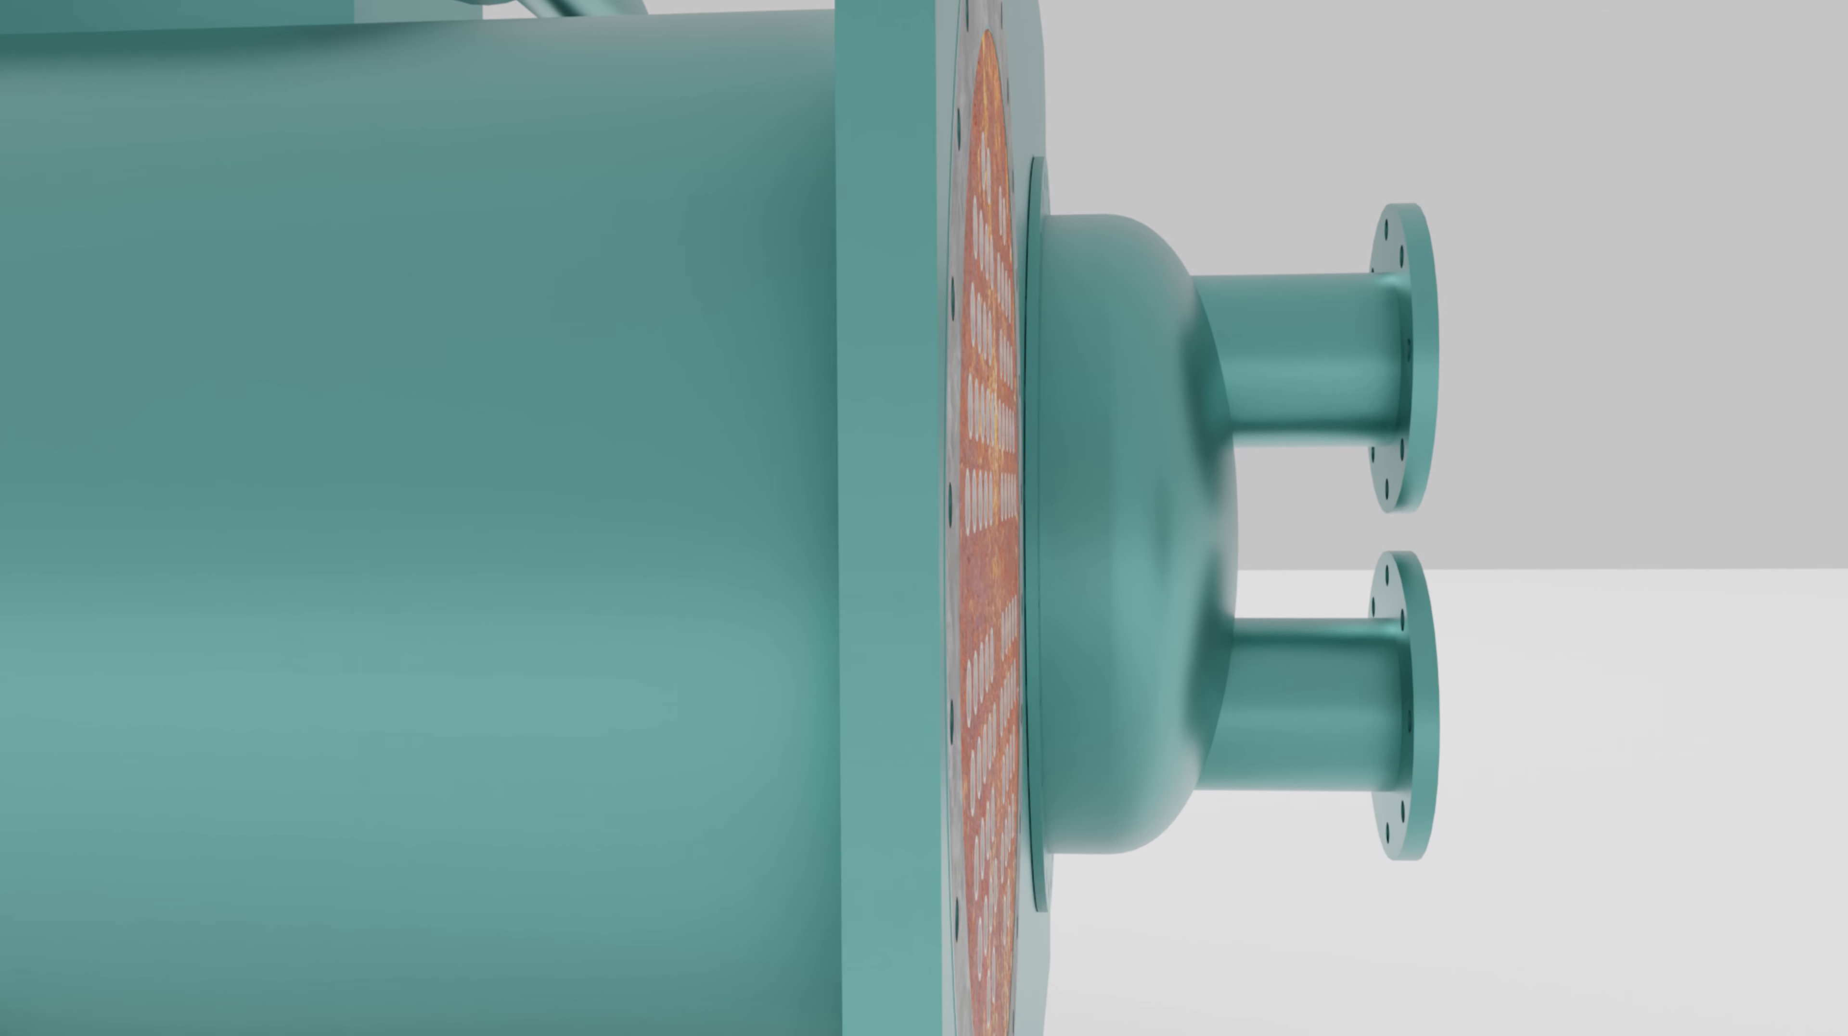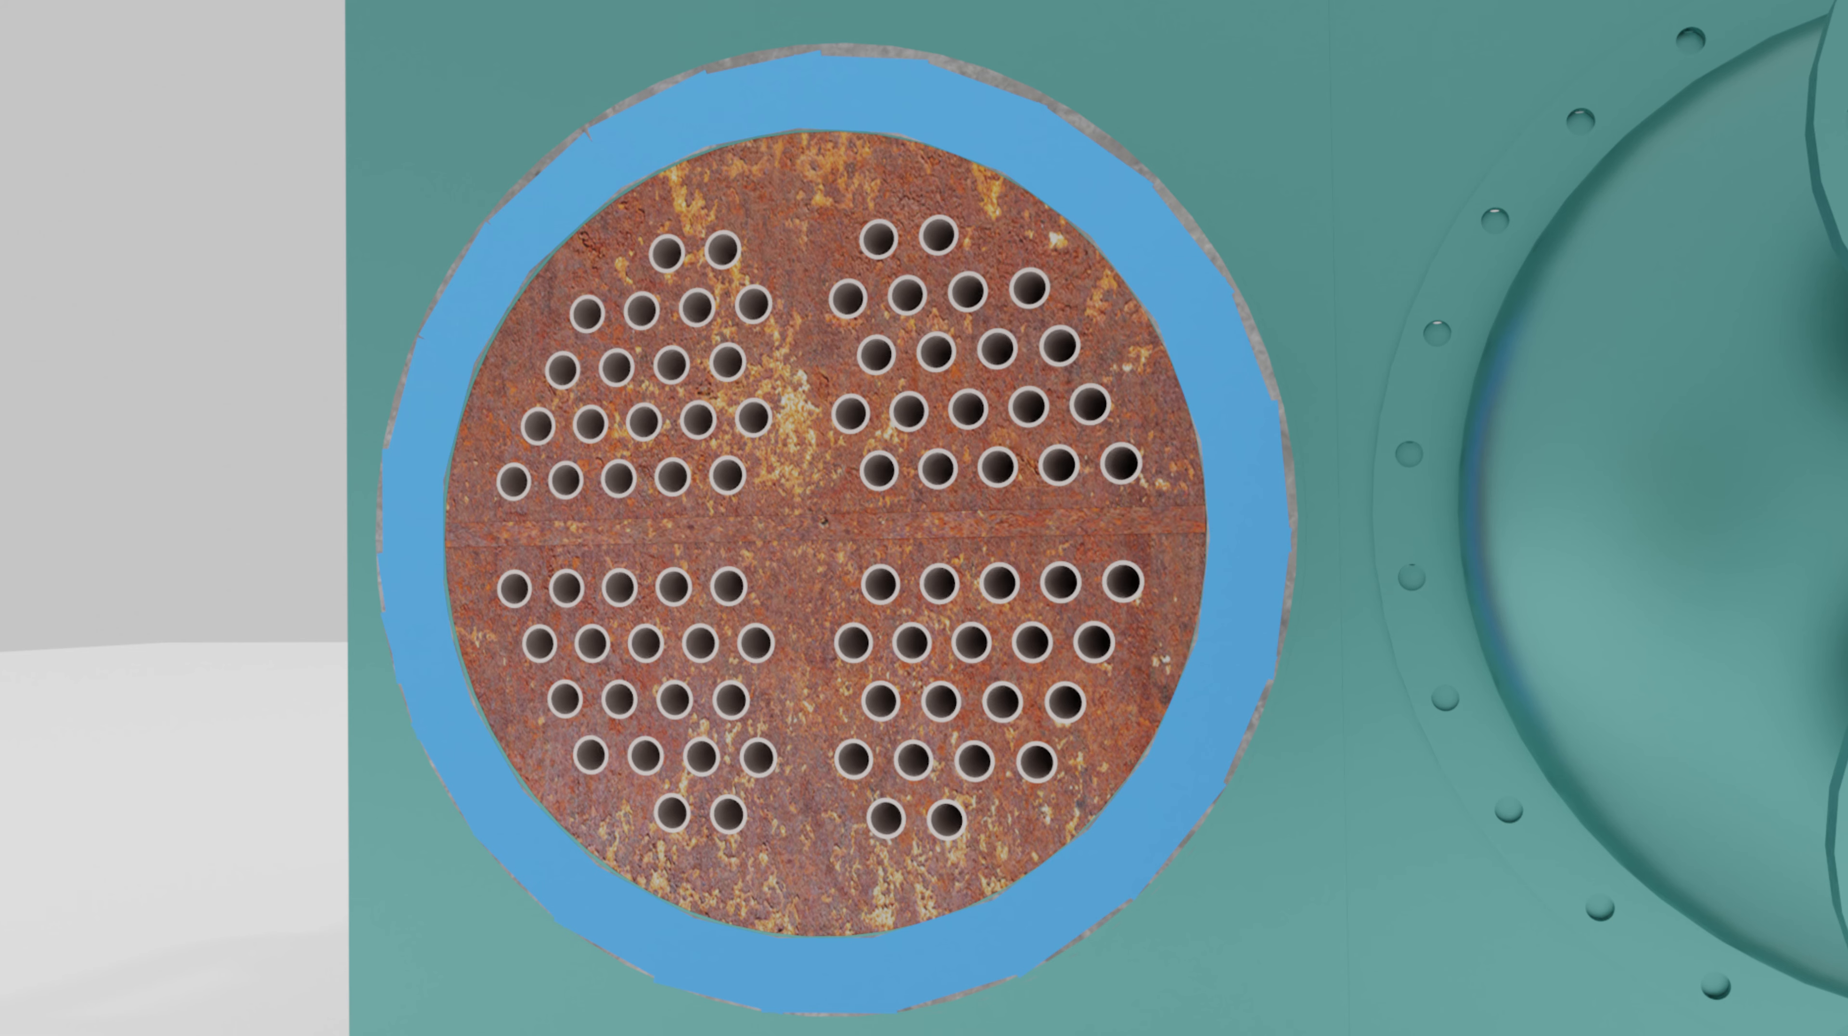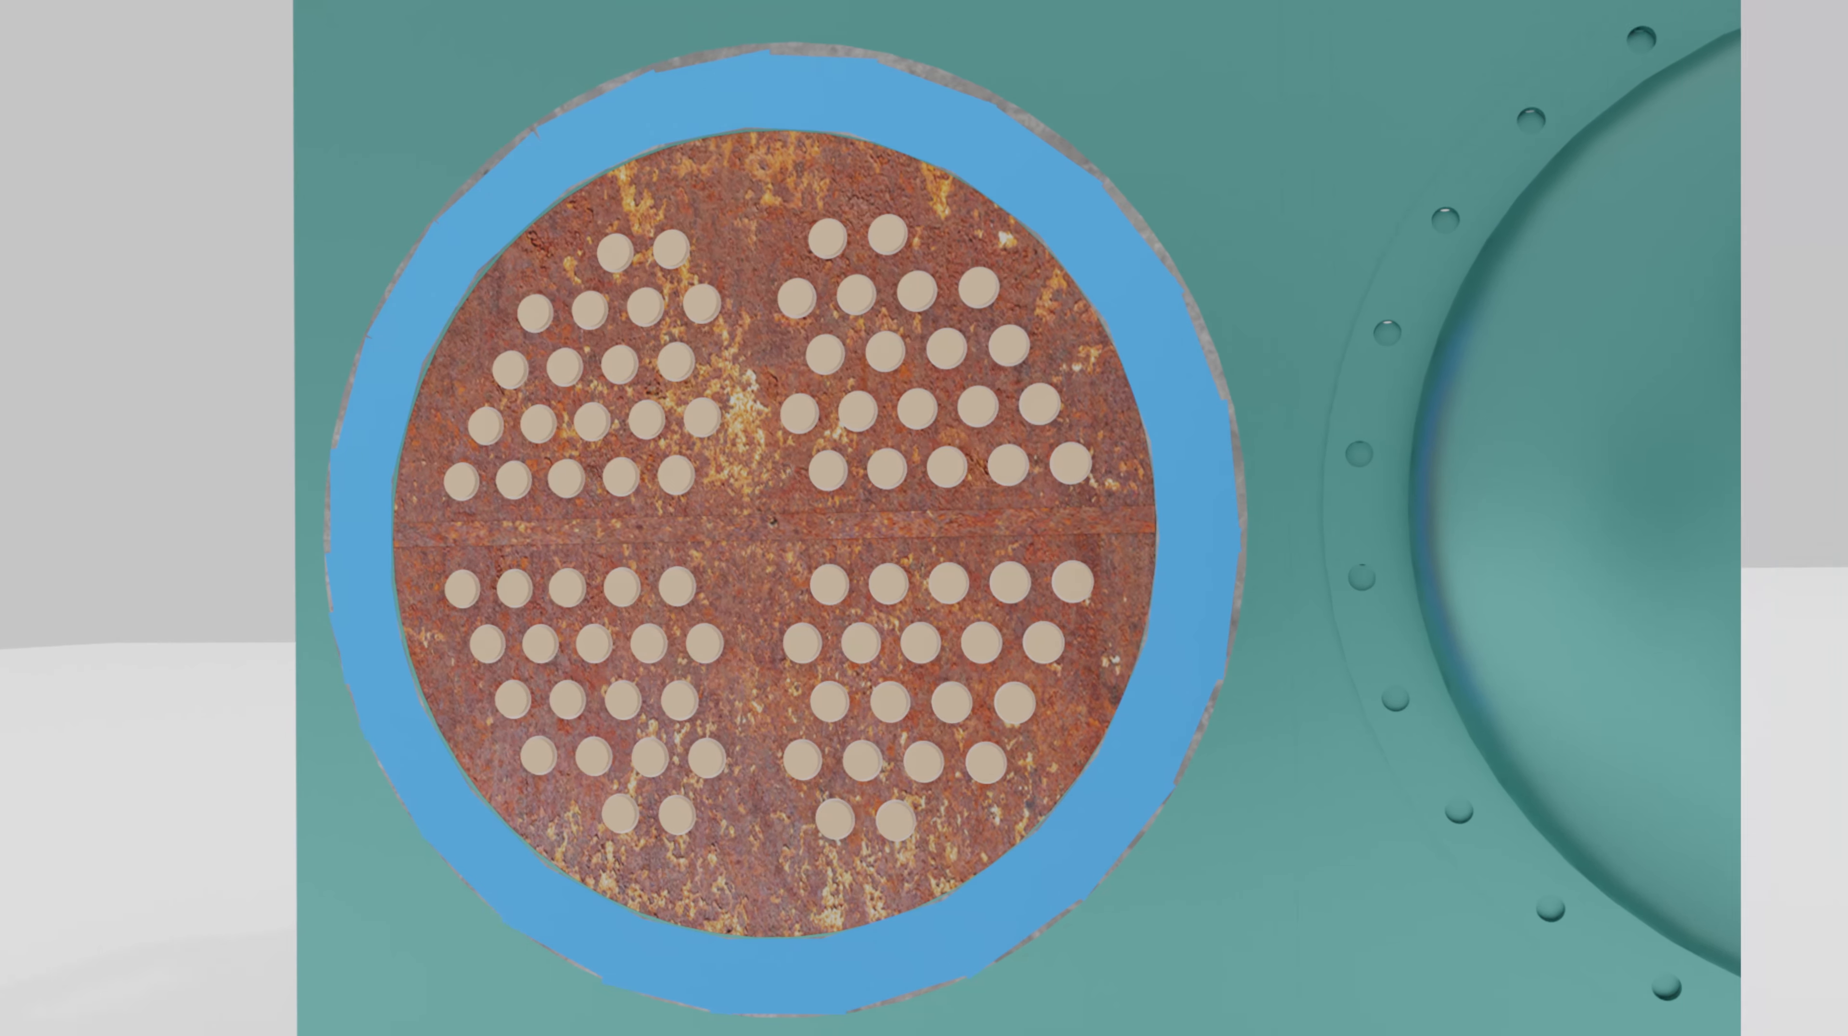Using fit for service coating and rebuilding materials and bespoke application techniques, before materials are applied, the damaged area must be identified, taped, and deemed mechanically sound. It is important that the internals of the tubes are protected before any mechanical preparation is carried out on the tube sheets. Corks can be used for this purpose.